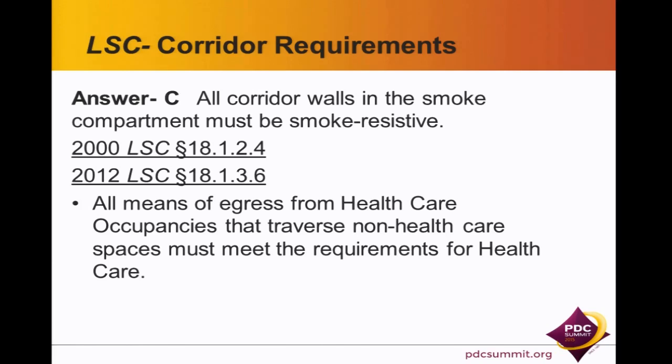So if you want to plant a seed, July 6th is the deadline for public input to the next edition of the Life Safety Code. And from a design standpoint, your question, sir, I think that sometimes in a situation like that where you have a large floor, it might warrant constructing a small smoke barrier so that you limit the area that you're responsible for protecting. Save a lot of money with door latching too.